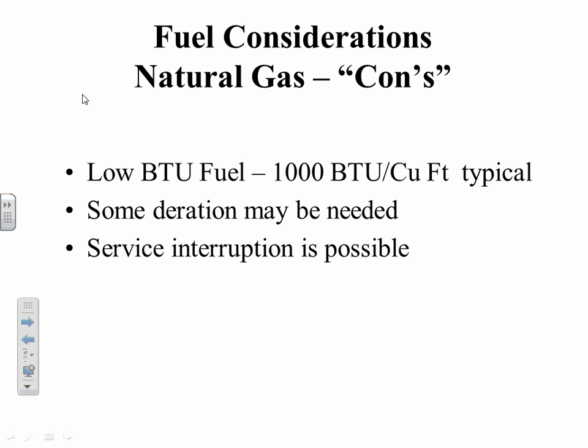On the con side of natural gas, it is probably the lowest BTU fuel, so it's got the lowest amount of energy, so we might derate that a little bit. And as I mentioned before, service interruption is possible, especially in the seismic zones.